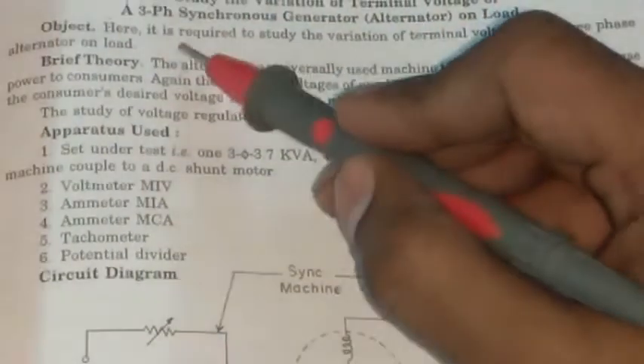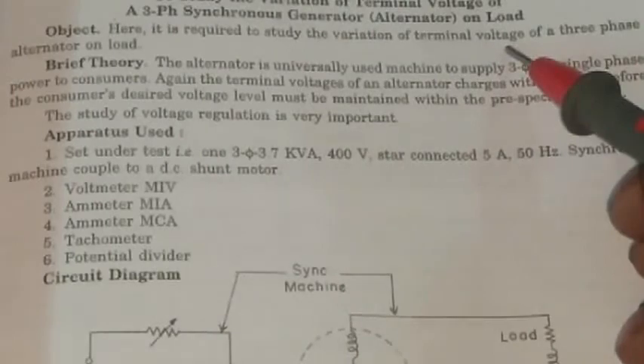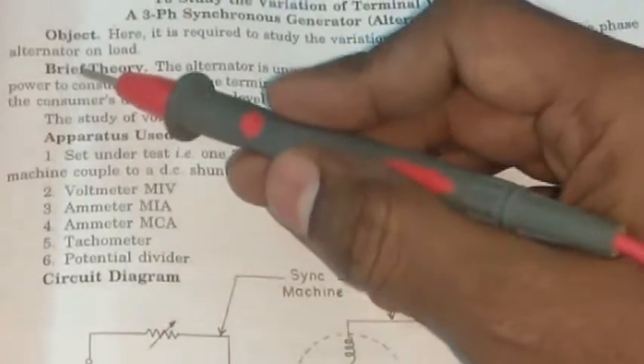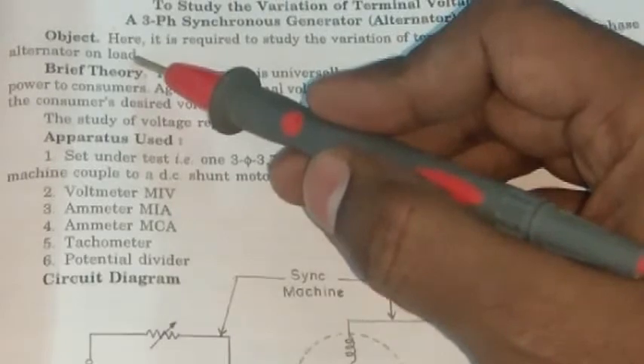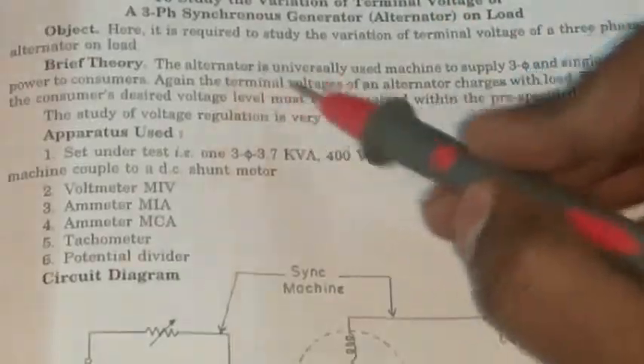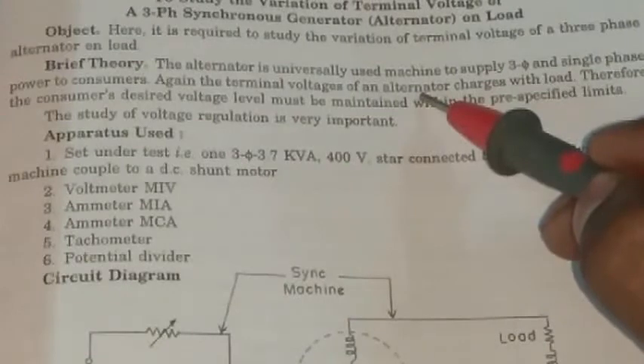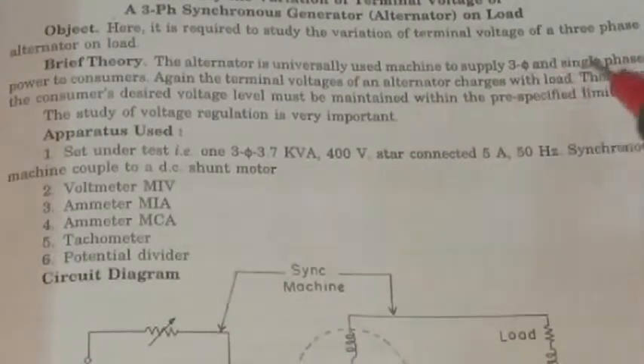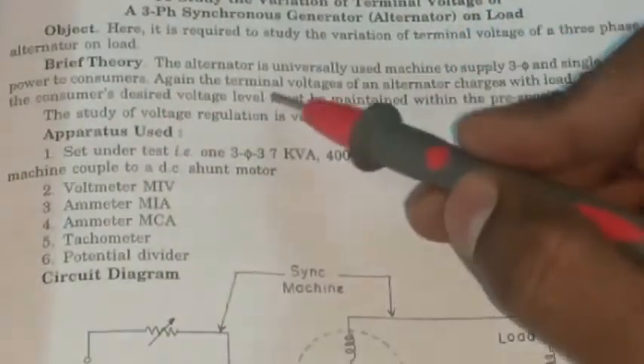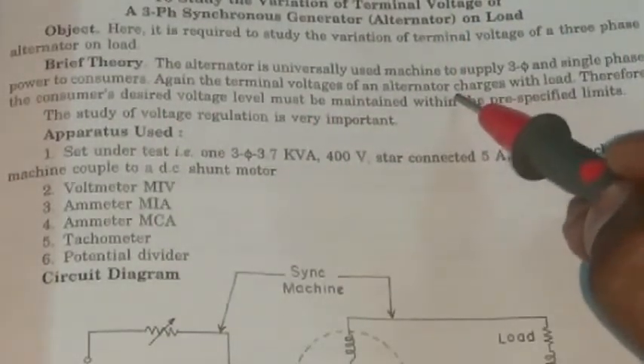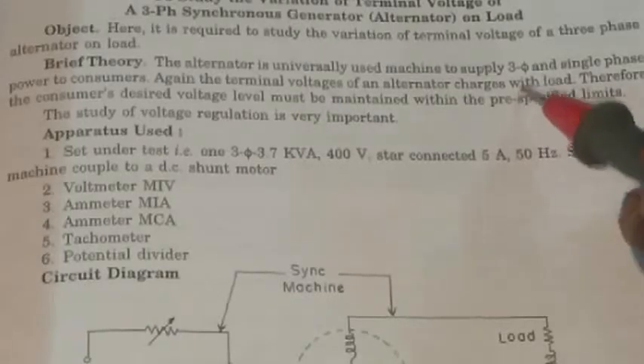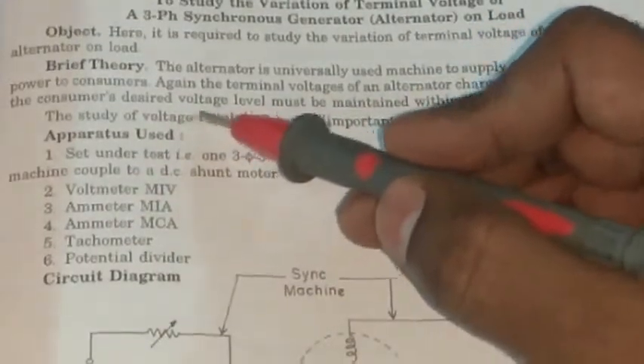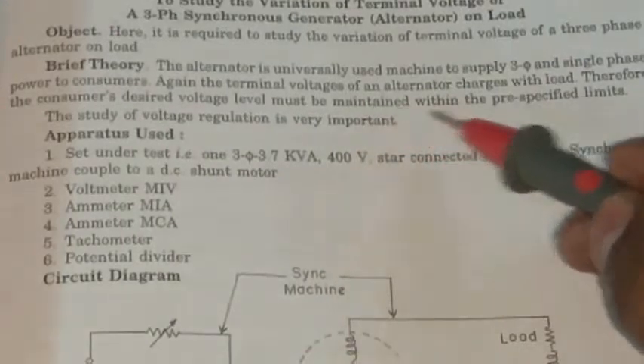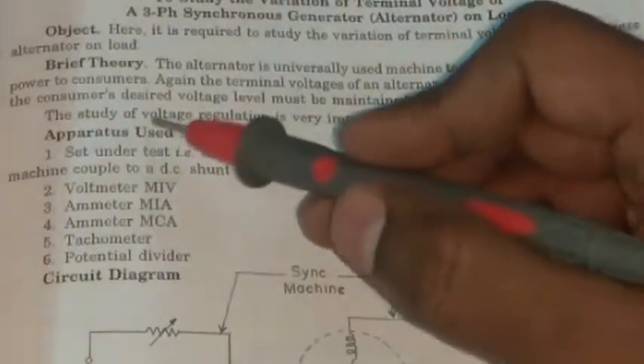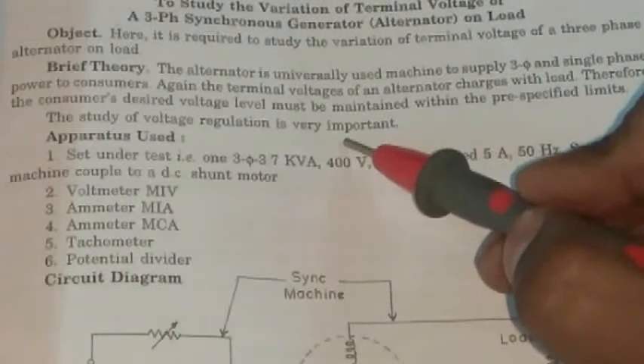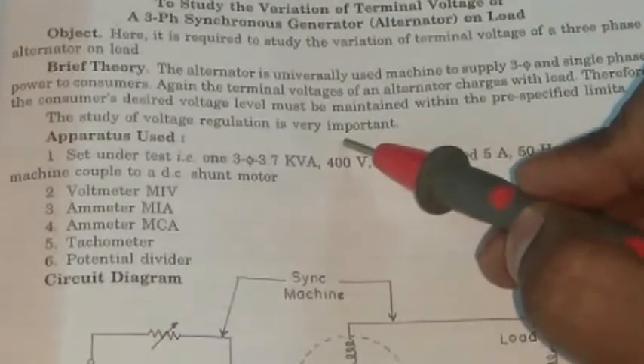This test is required to study the variation of terminal voltage of a three-phase alternator on load. This variation is what we call the regulation. The alternator is a universally used machine to supply three-phase and single-phase power to the consumer. The terminal voltage of the alternator changes with the load. Therefore, the consumer's desired voltage level must be maintained within the specified limit. The study of voltage regulation is very important. So, we are going to perform the voltage regulation.